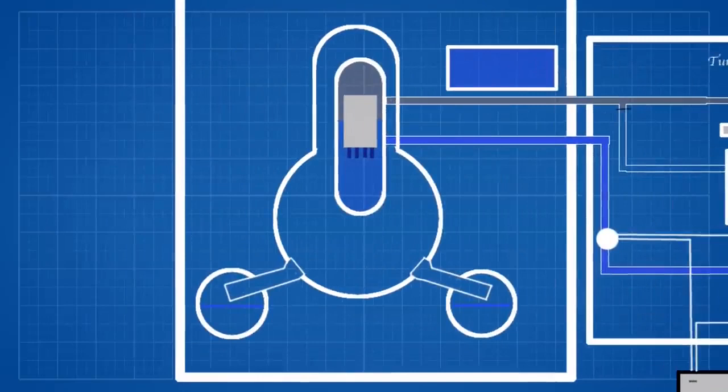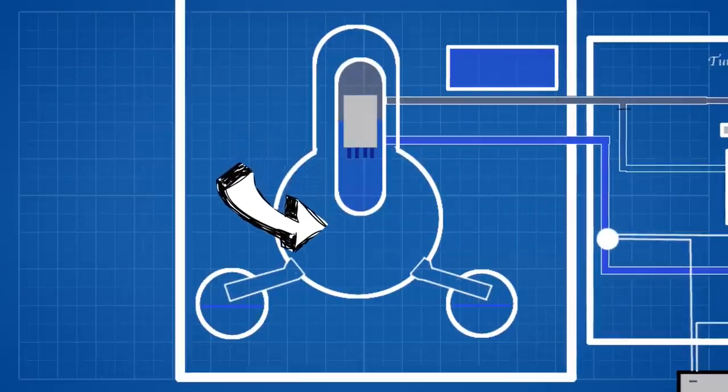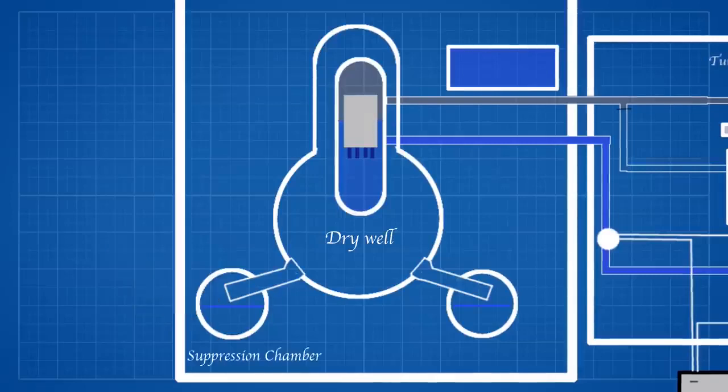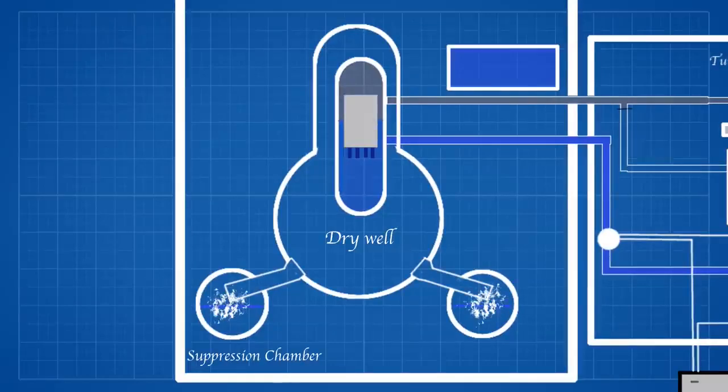The PCV has two major compartments. The reactor vessel is located in the dry well. The DW is connected to a second compartment, the suppression chamber, which holds a large amount of water and enough space to suppress pressure increases. The water within the suppression chamber can be used to scrub radioisotopes from any gases released within the containment vessel.